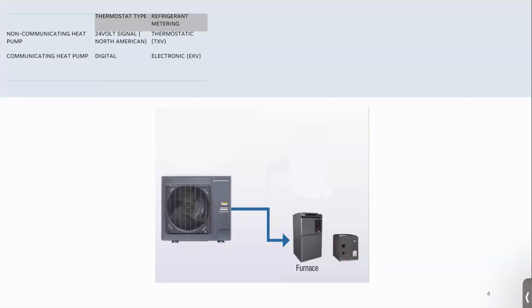Communicating heat pumps, digital systems, been around forever. Well, not forever, sorry. Long, but more in the air conditioning industry. We've had them. Mitsubishi, Fujitsu, a lot of those use zeros and ones to send data, and not 24-volt signals. And the refrigerant metering would be different. You'd have a thermostatic TXV on the non-communicating heat pump and an electronic EXV on the communicating heat pump. I'm going to keep fairly brief on that. You can go into the weeds with all sorts of things, but just know that the complexity grows considerably when you get into a communicating heat pump.